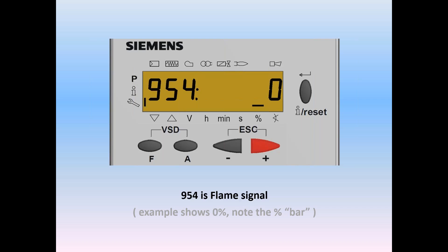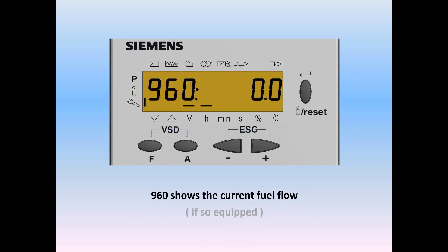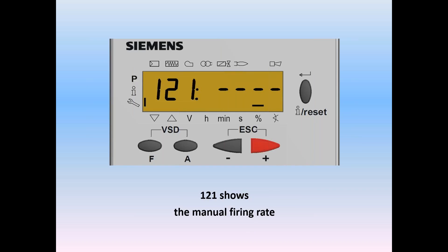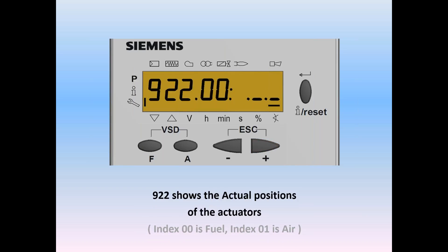Push the plus key to move on, and now we get parameter 960, which shows the current fuel flow — in this case 0. Do a plus to move to the next screen: parameter 121, which shows the manual firing rate — in this case we don't have one. Do the plus key and we move on to 922, which shows the actual positions of the actuator. This parameter has indexes: 0,0 is fuel and 0,1 is air.